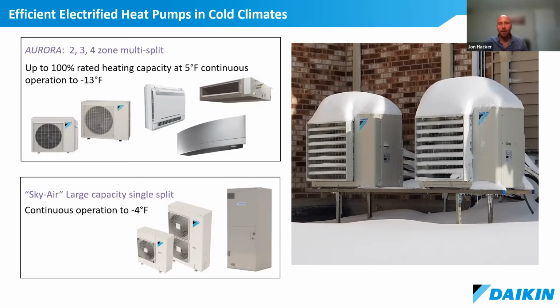And as I suggested, they can provide 100% of their rated heating capacity to 5 degrees and provide continuous heating operation down to -13 Fahrenheit. And those are more of a ductless product. Again, can be multi-zone. We do offer some low static, short run ducted configurations for that as well. And then on the bottom left, I'm showing our Sky Air product, which is a traditional centrally ducted system with an inverter, and that provides continuous operation down to -4 degrees Fahrenheit outside. Does an incredible job of maintaining heating capacity all the way down to -4. And both of these, depending on the application, have become really popular in and around New York City.